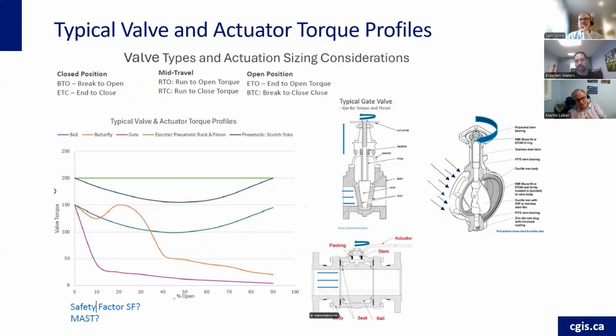Years ago, I did some sizing on a big ball valve out in Alberta. It was an exposed ball valve, at minus 40, minus 50. We were sizing close to, I think, 1.8 or 2 on those, because when the cold sets in, the ball gets squeezed, everything shrinks, so the torque to run the valve gets a lot higher. So it's all based on the application. There are some guidelines for factors of safety. And yes, MAST is critical that we don't exceed on the valve, to prevent damage to the valve. If you exceed the MAST on the valve, you could potentially damage it.